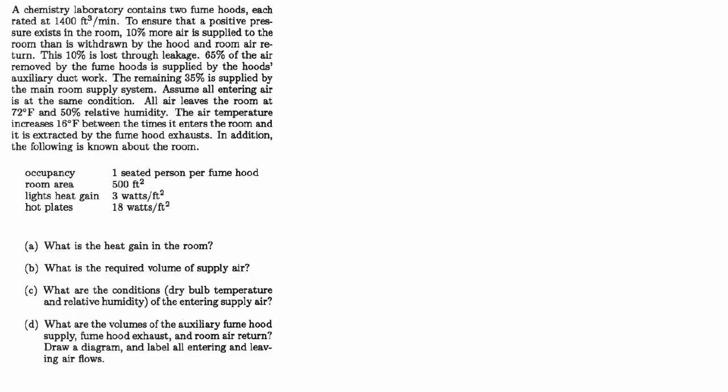The remaining 35% is supplied by the main room supply system. Assume all air entering is at the same condition. All air leaves the room at 72 degrees and 50% relative humidity. The air temperature increases 16 degrees between the time it enters the room and is extracted by the fume hood exhausts.